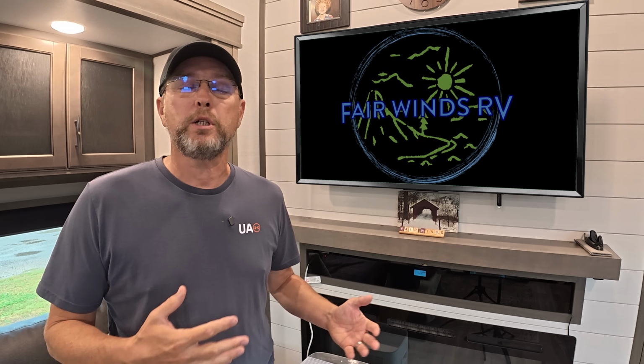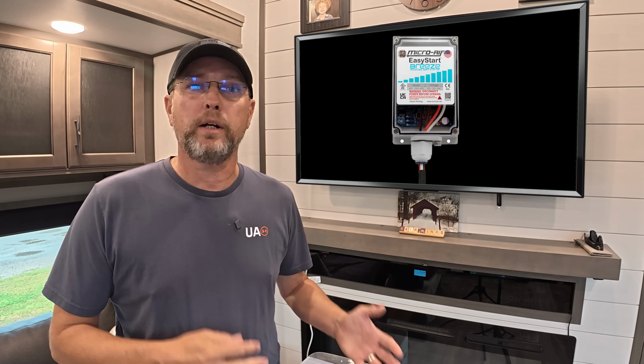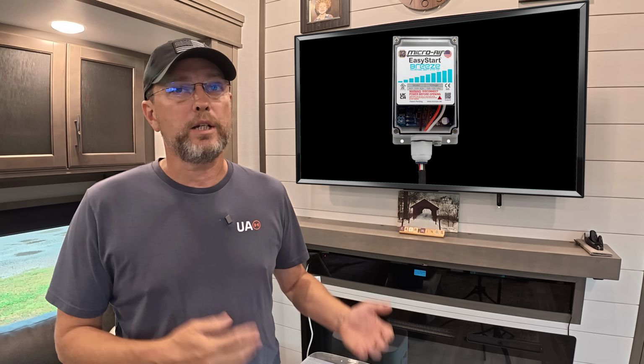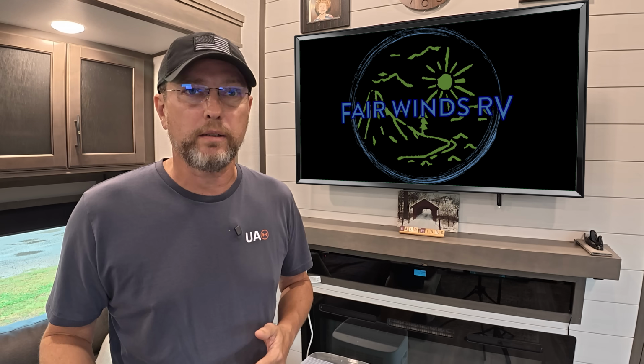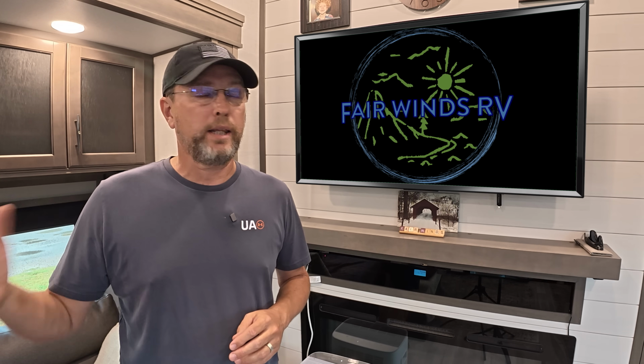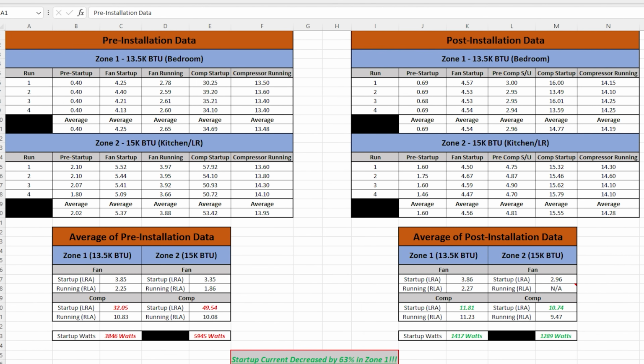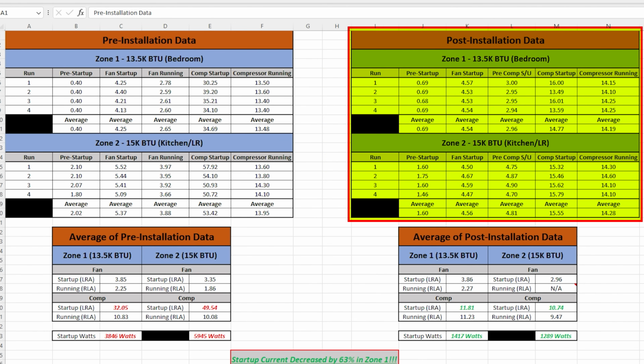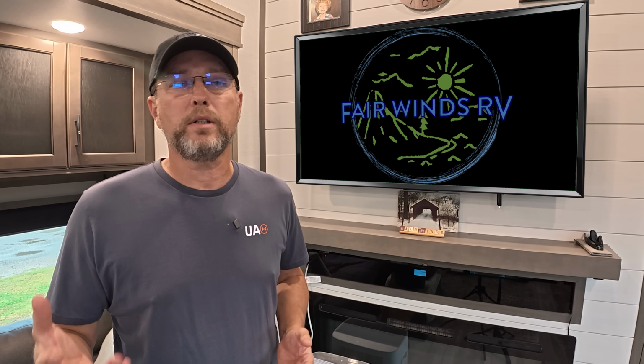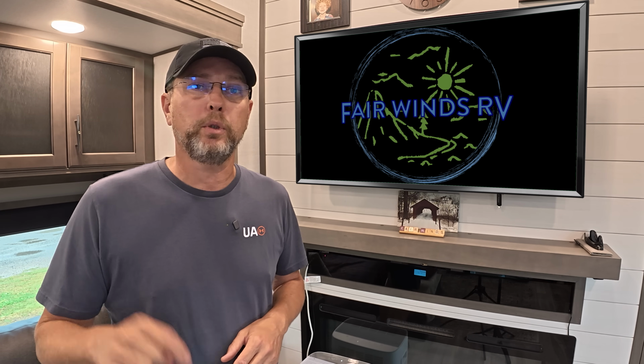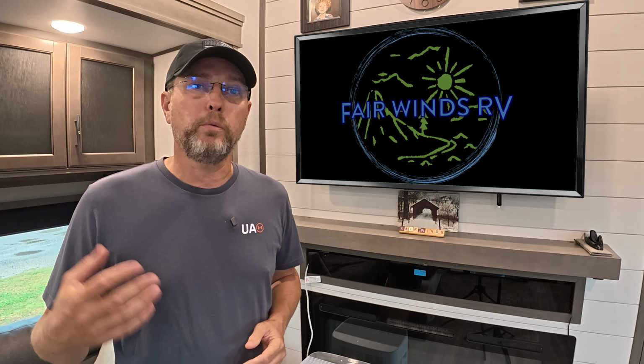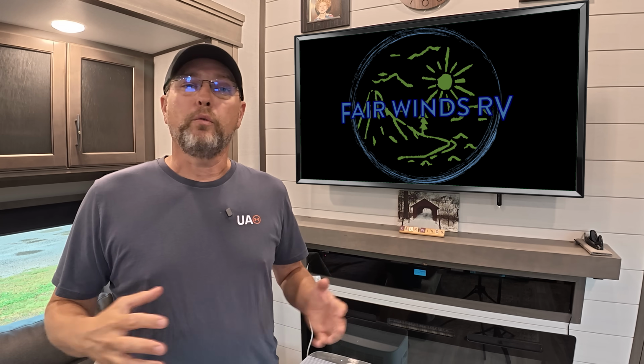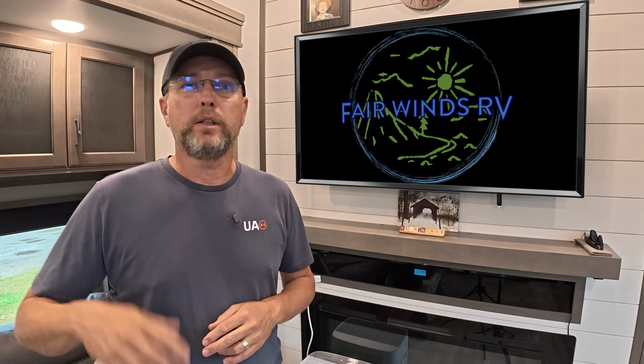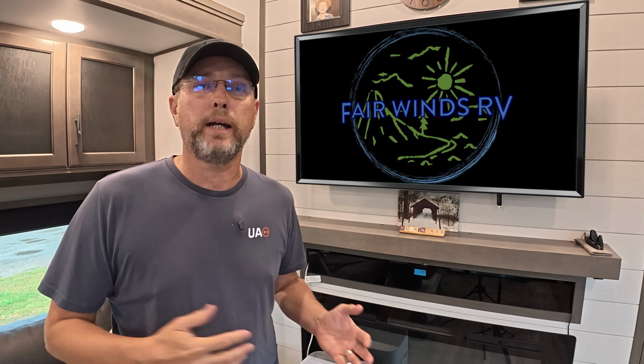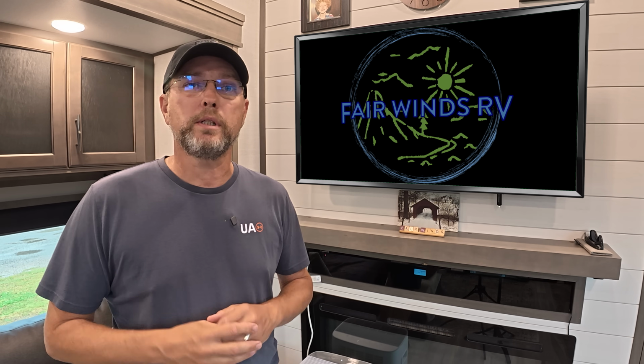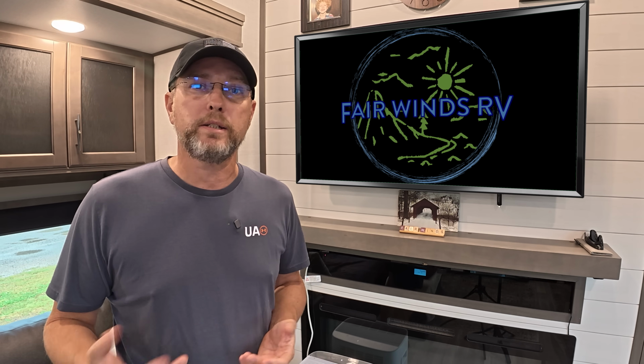So to minimize how much power these things draw when they start up, we turn to things like the MicroAir Easy Start soft starters. These can decrease that initial power surge by up to about 70%, and trust me, that's not a myth. We actually did a video on this a couple years back, testing the starting surge on our air conditioner both before and after installing one of these MicroAir Easy Start units. I won't get into the details, but I'll link that video below. I was really surprised by the results after installing that soft starter. It's not just about starting AC units on a limited power supply, it's about protecting all the components inside your air conditioner to help it last as long as possible.